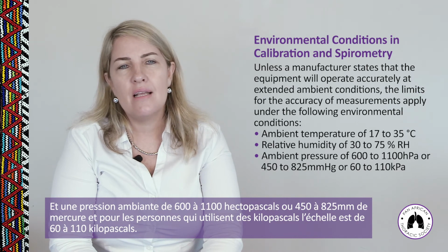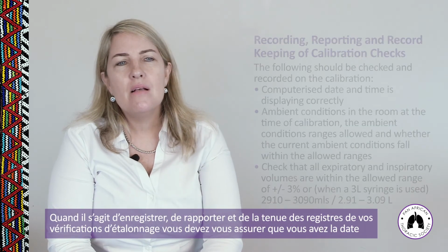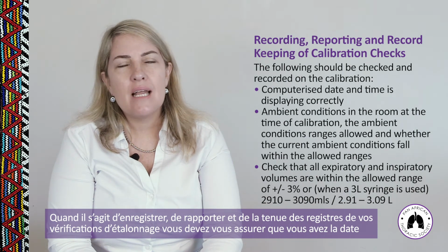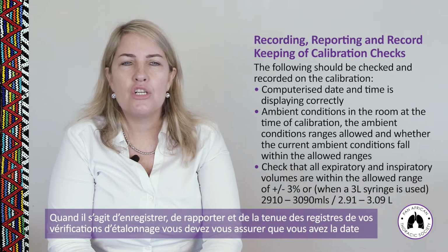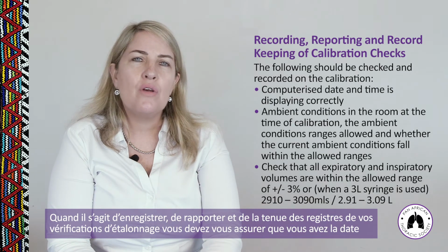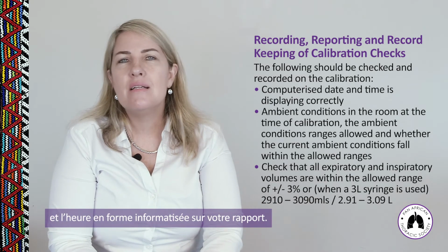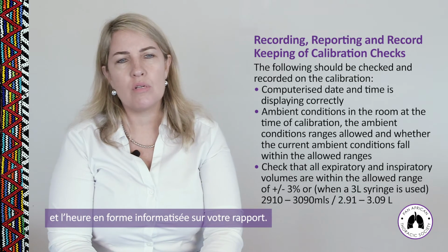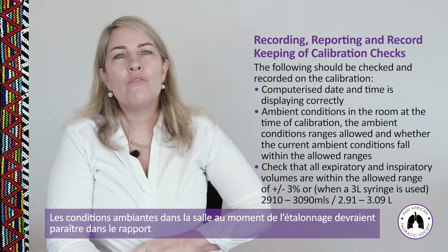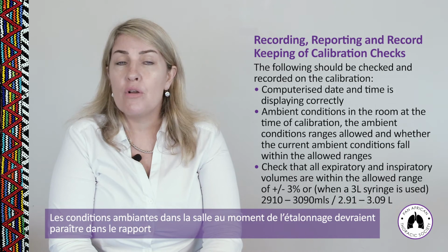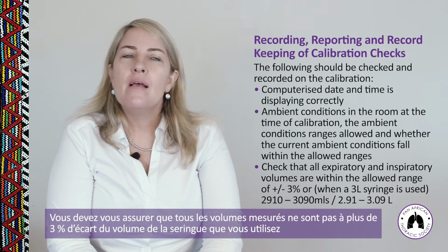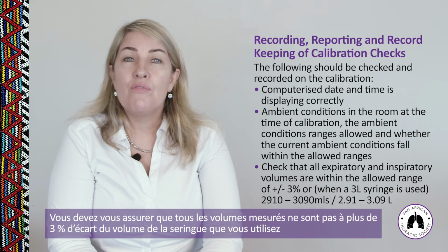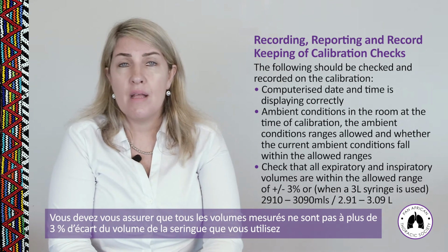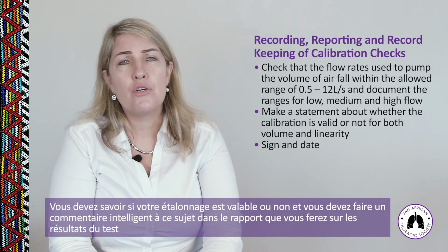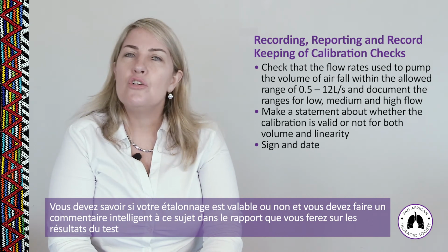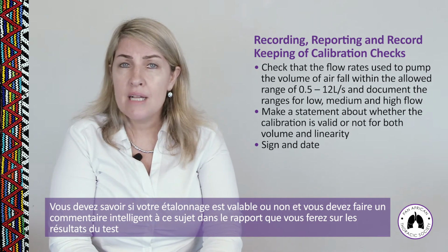So when it comes to recording and reporting and keeping records of your calibration checks, you need to be sure that you have a computerized date and time displaying correctly on the calibration report itself. The ambient conditions in the room at the time of calibration should be noted somewhere on the report. You need to make sure that all the measured volumes fall within 3% of the syringe volume that you are using. You need to make sure that if you're doing a linearity check, that you used low, medium, and high flow rates.